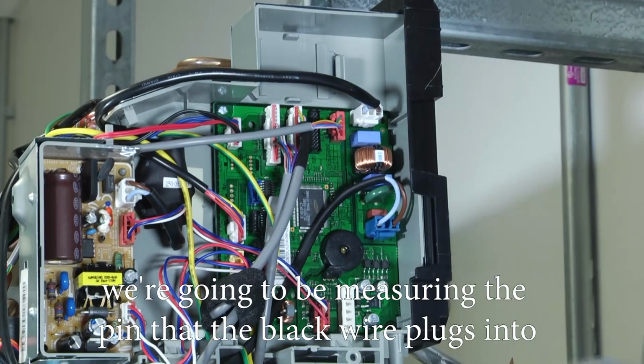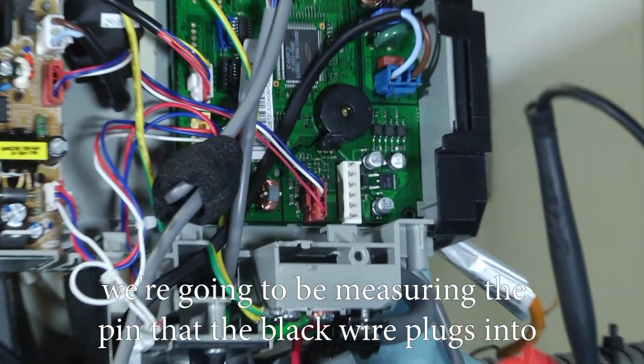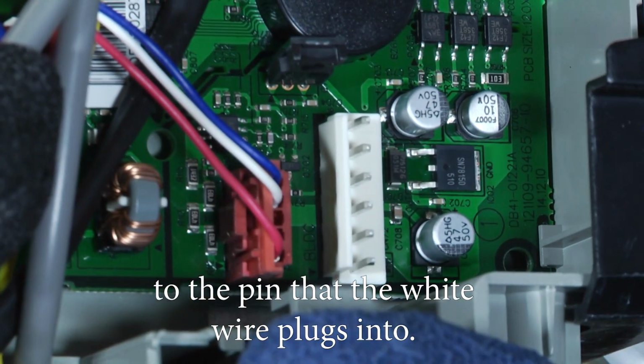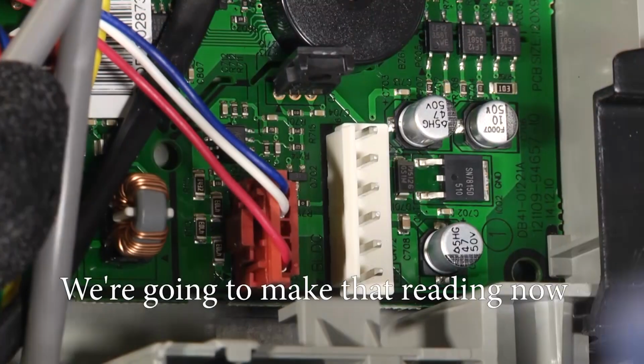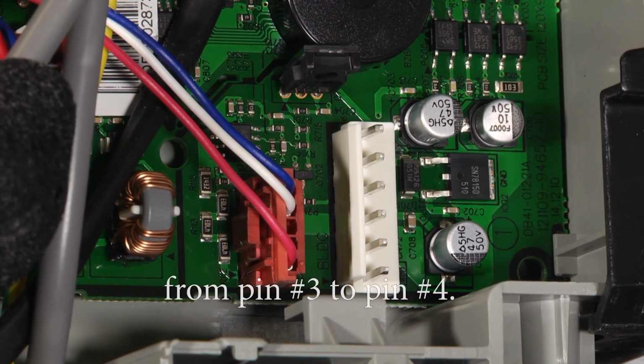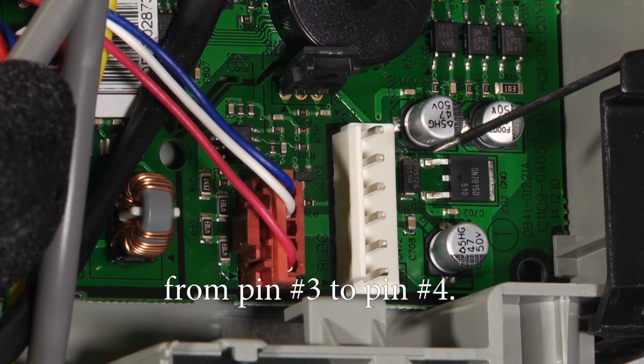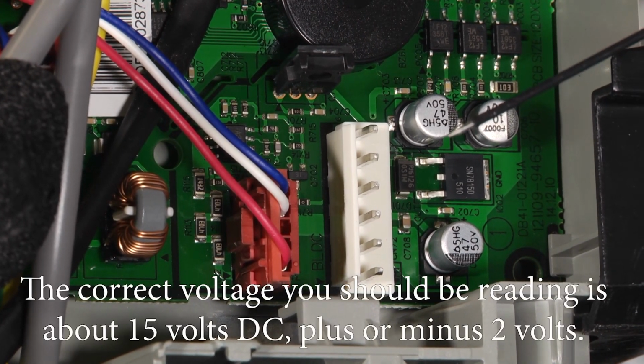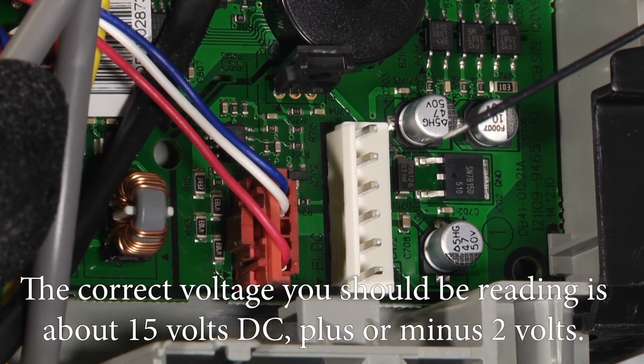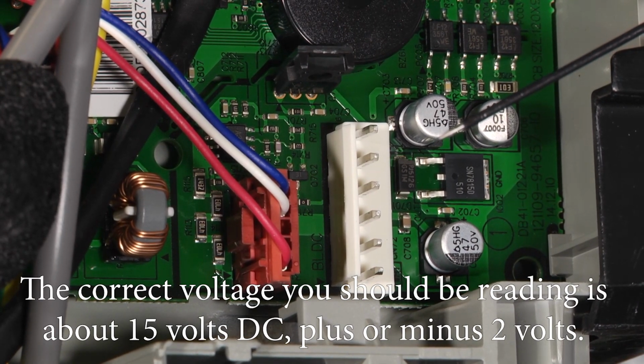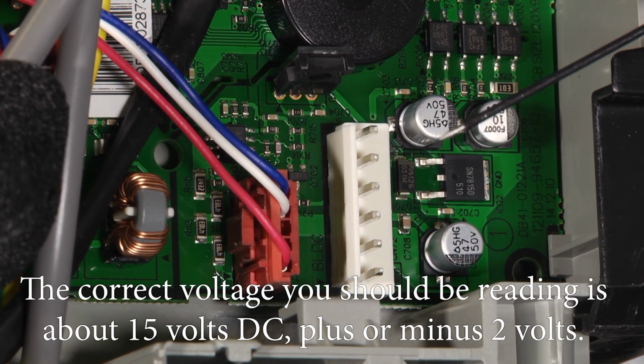Okay, on the next one, we're going to be measuring the pin that the black wire plugs into to the pin that the white wire plugs into. We're going to make that reading now from pin number 3 to pin number 4. The correct voltage you should be reading there is about 15 volts DC, plus or minus 2 volts.